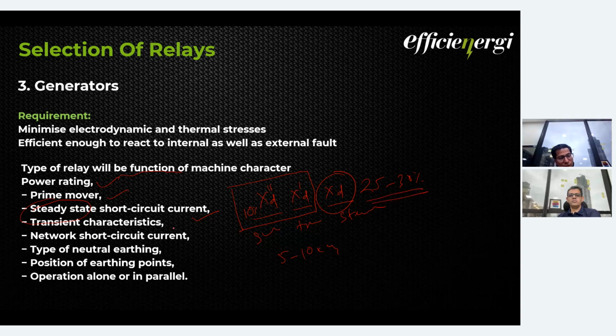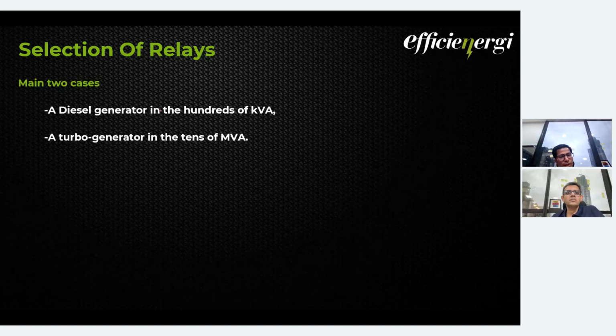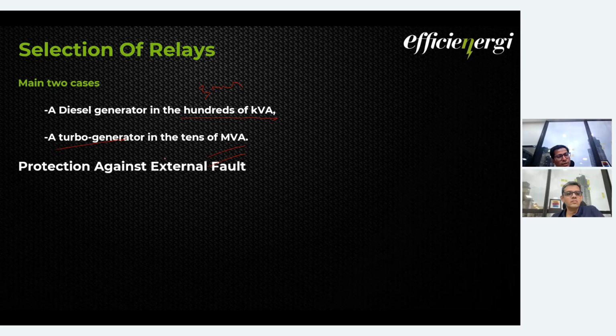Sometimes the steady state current can be less than the rated current of the generator. So it is very difficult to analyze or to trip the generators in a steady state zone. So there are two main cases we have to consider. One is diesel generators, which are of hundreds of kVA, 3 MVA maximum I have seen. Then turbo generators, where we have tens of MVA.